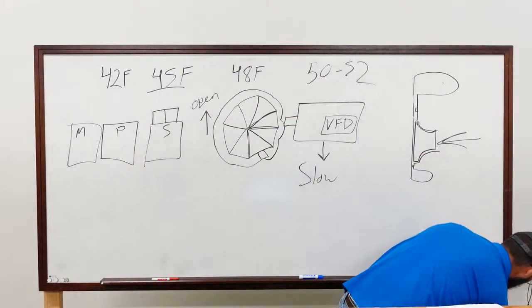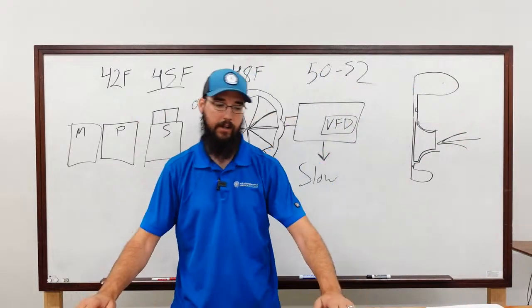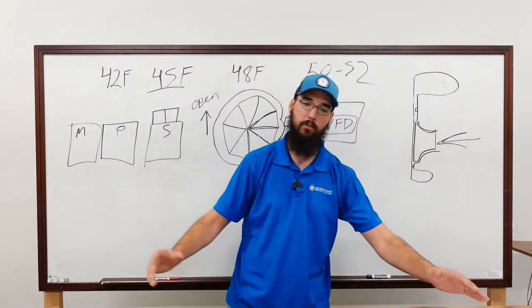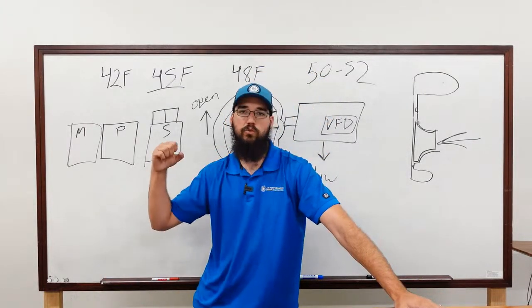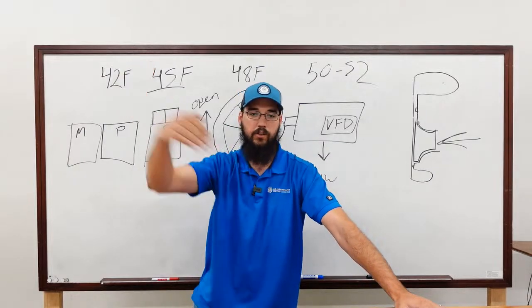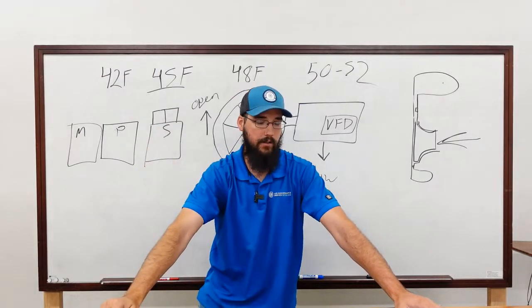So in an extreme case, let's say you had really high condenser water because the cooling tower had issues, you had some kind of flow problem, whatever, right? That thing will go straight through stall and just into a surge rapidly. It can happen that quick.